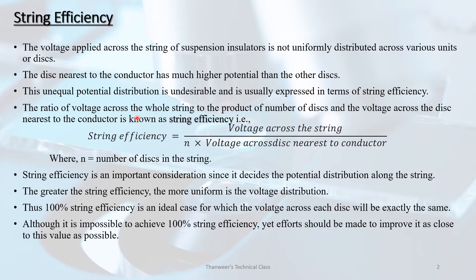The ratio of the voltage across the whole string to the product of number of disks and the voltage across the disk nearest to the conductor is known as string efficiency. String efficiency equals voltage across the whole string divided by the product of number of disks (n) into the voltage across the disk nearest to the conductor.